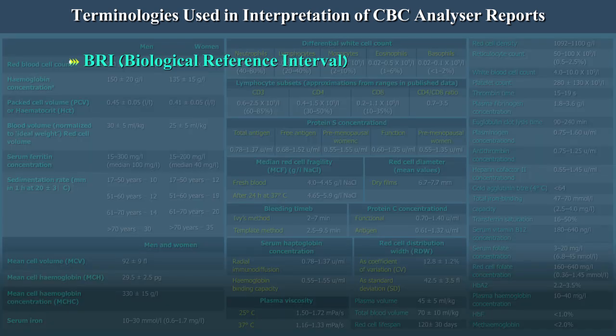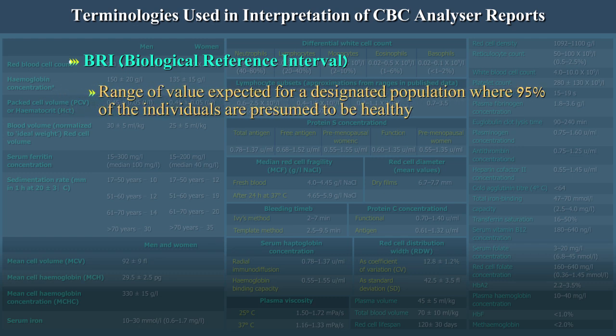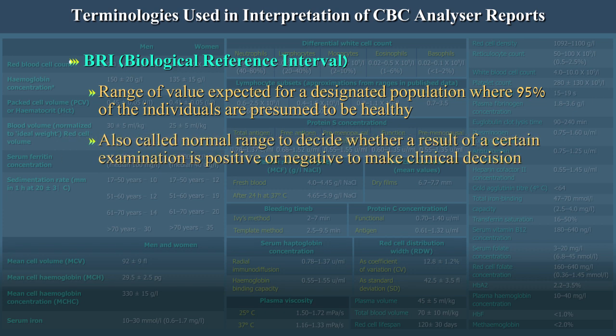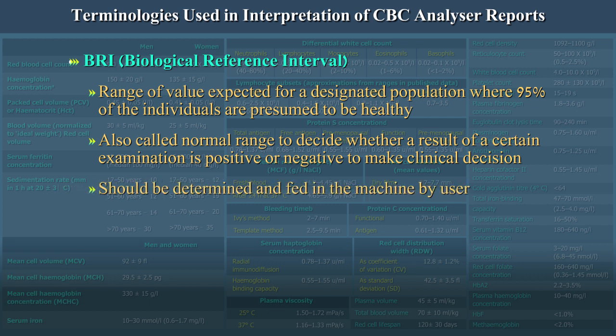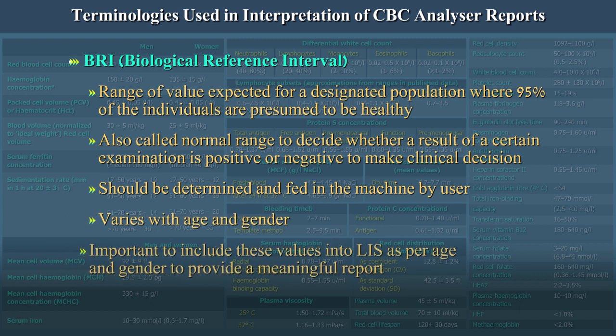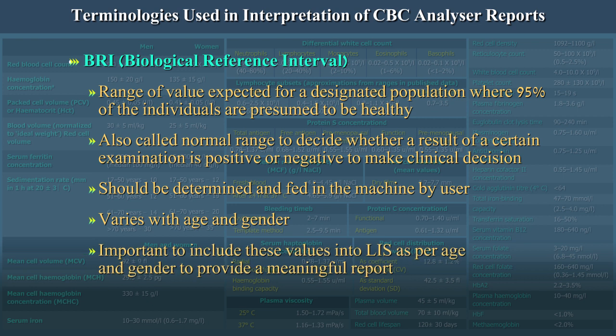Biological Reference Interval, i.e. BRI. It is a range of values expected for a designated population where 95% of the individuals are presumed to be healthy. This is also called the normal range, used to decide whether a result is positive or negative to make a clinical decision. It should be determined and fed in the machine by the user. The BRI varies with age and gender, and it is important to include these values into your LIS as per age and gender to provide a meaningful report.